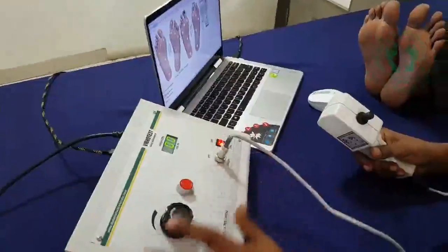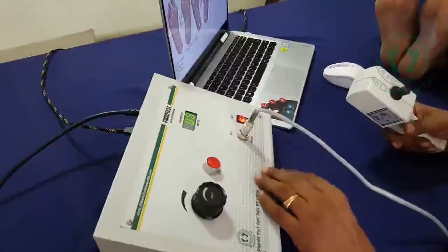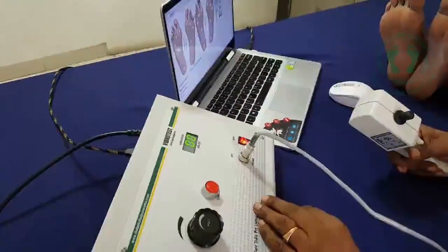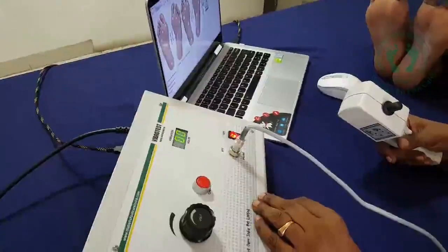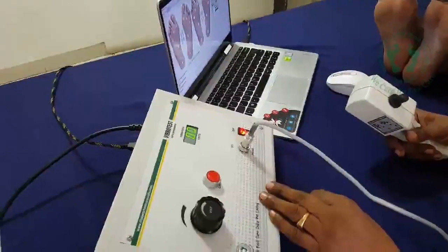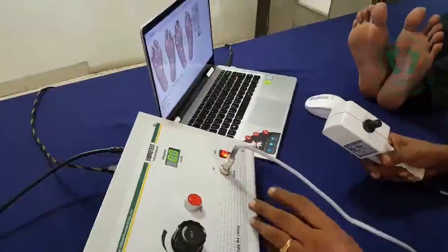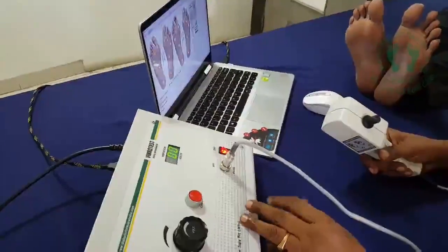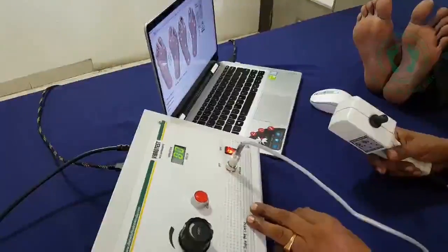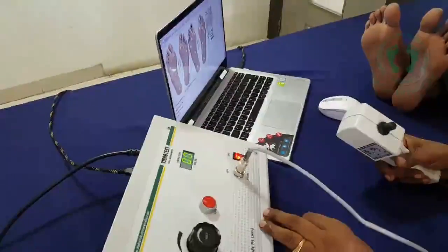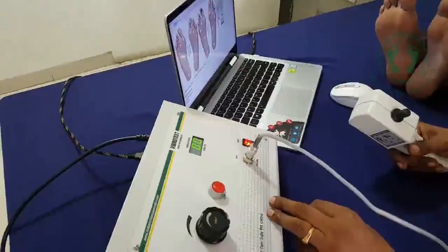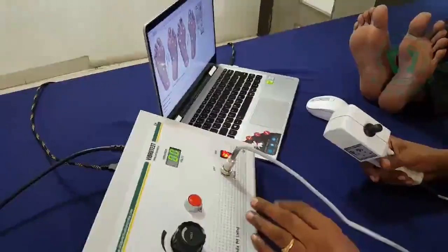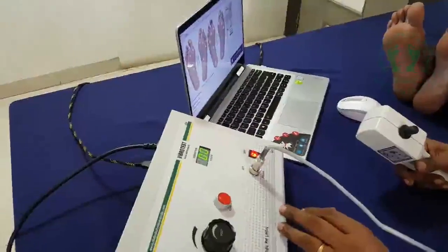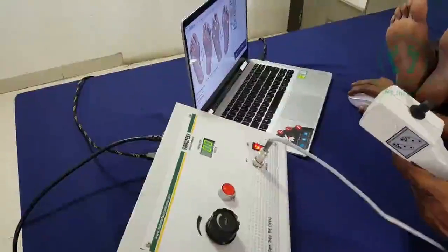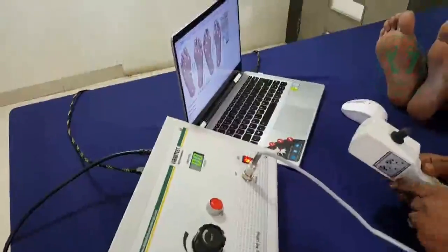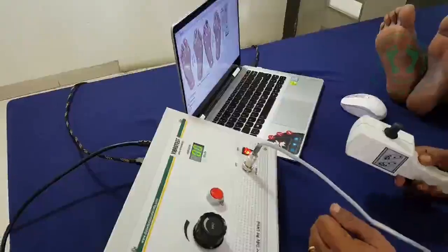We will test this VIBROTEST device on the patient, and also we will use the computer to record the data. Before testing it, we need to educate the patient so that they feel the vibration pattern very clearly. Only then will the reading be much better. Normally what we do is show them with a little high intensity on the hand, since the hands are not much affected, so they can feel the vibration and differentiate between the touch and the vibration. With that, when we test it on the foot, they can easily understand the vibration pattern. Then the results will be much better.